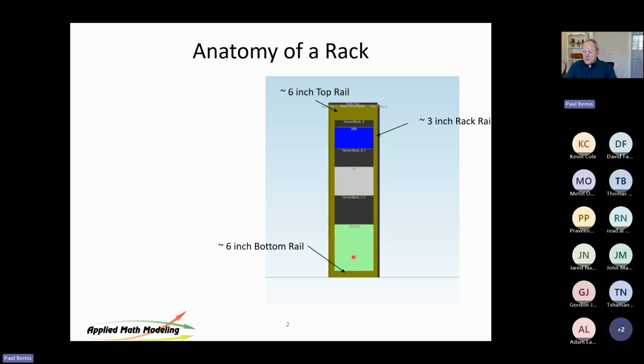So it's really the servers. When we talk about rack inlet temperature, it's not the rack itself we're measuring, it's the server inlet temp, the average server inlet temp. And you see here, I've defined this one. You can do this in CoolSim. You can define your equipment. So I've got an IBM stuck in there. That looks like a 5U. Got an HP stuck in here. That's a 5U. And then storage down here. That looks like 15, probably U. They all come in U's. One slot, I believe the number is 1.75 inches. I haven't looked at it in a while, but I think that's it.